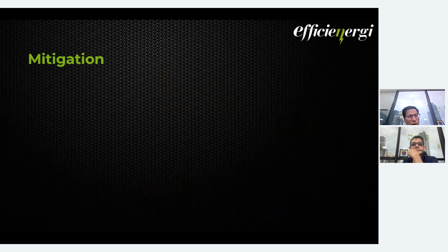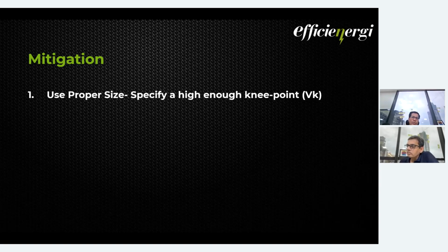Okay, so mitigation. The first mitigation is to use proper sizing, that is, use a knee point voltage high enough so that saturation will not occur. But it is not always recommended, or not always practically possible, because if there is a heavy fault and you have to build a CT without saturation, with a high saturation voltage point, then the CT size becomes almost equal to your switchgear size. To accommodate those kinds of CTs, indoor or outdoor switchgear is not always possible. So to the extent you can, you have to size it properly.